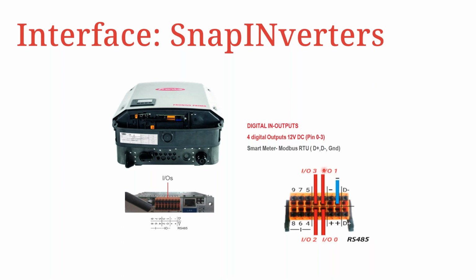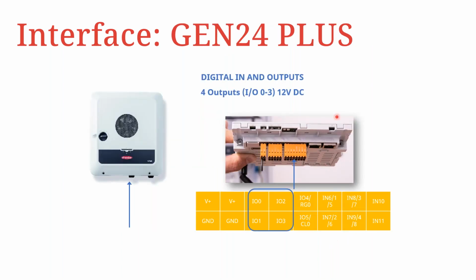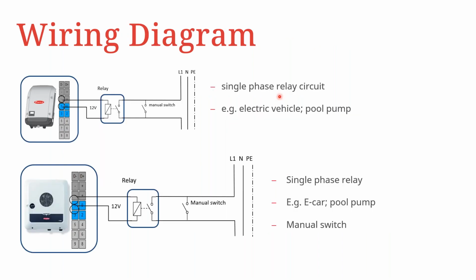When it comes to the Gen 24 Plus, the same kind of configuration is possible. The only difference here is that the Gen 24, instead of the Data Manager, is using a Pilot. But in terms of the available outputs, we still have 4 of them. So you can see them starting from IO0 to IO3. The connection diagrams for both the Snap inverter and the Gen 24 are very similar.